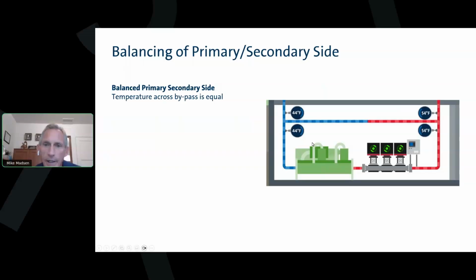Yeah, absolutely. And another thing we can do is on heating systems, this shows chilled water going out into the system. We can maintain a 10-degree delta T on our primary loop. And in heating, we're probably using a 20-degree delta T on the secondary side. We can set the 20-degree delta T on the secondary side and a 10-degree delta T on the primary side. So very, very flexible. Yeah, we talked about that.